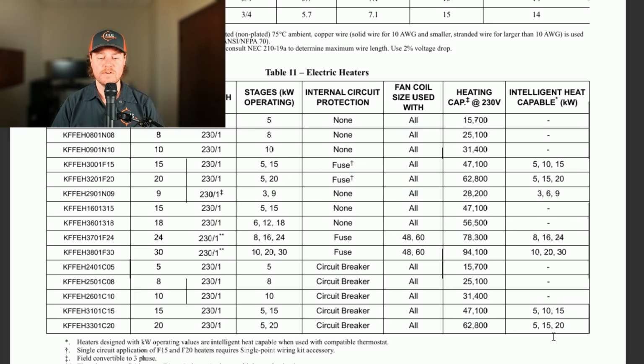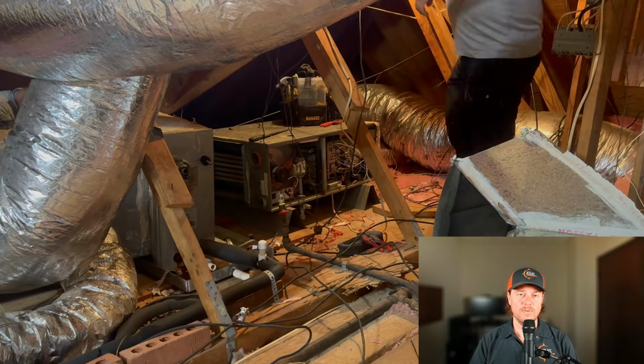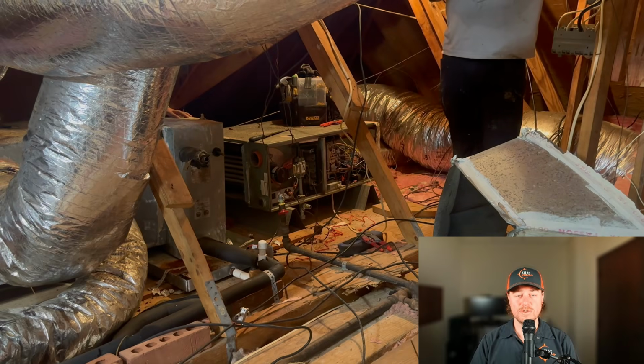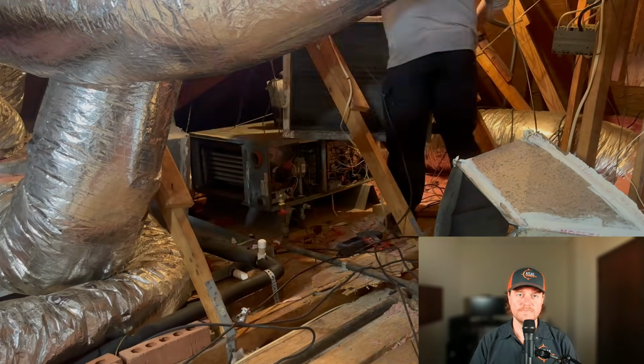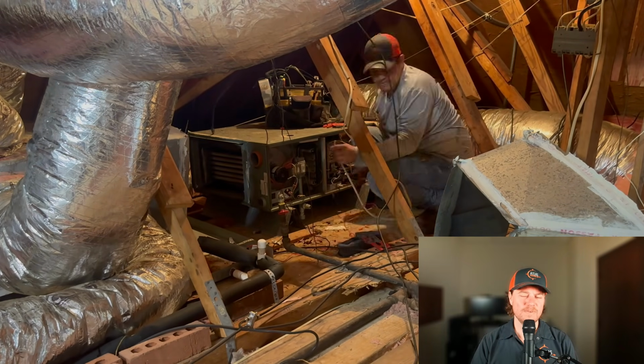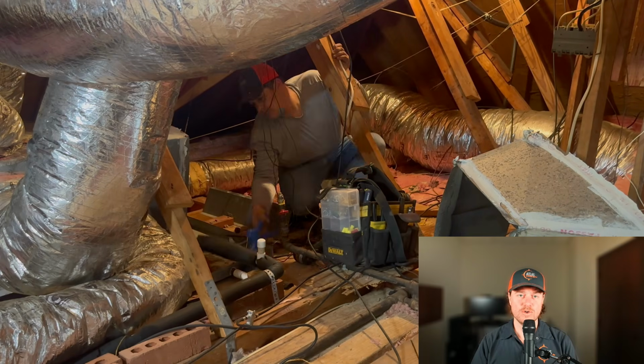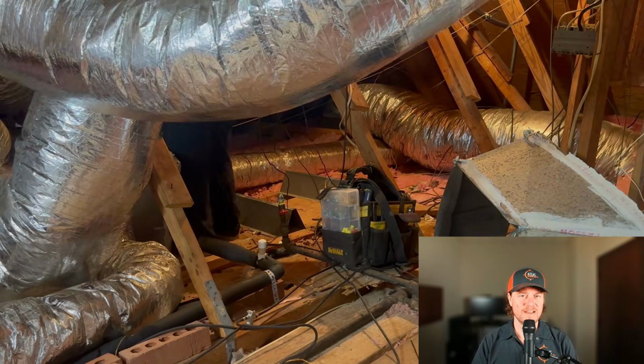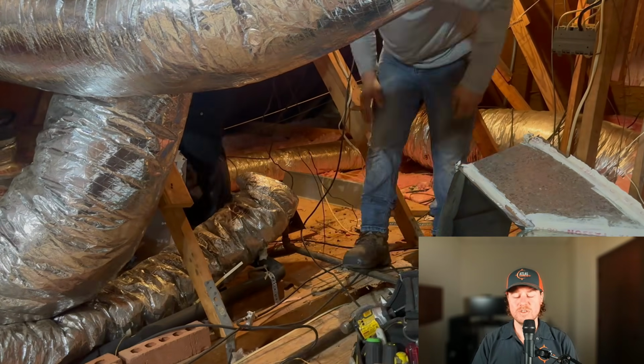Now I can design a small zone for 5 kW heating capacity, which ends up being around 30% of the overall capacity of the system. And that would be for a 4 or 5 ton system, which are the ones that are primarily used for zoning. Because the smaller and smaller system that you have, the less likely you'll probably need to zone it. And for dual fuel applications, once again, we have to design for auxiliary heat, which puts us back at a modulating furnace. That being said, is an expensive zoning system like this one really worth it?